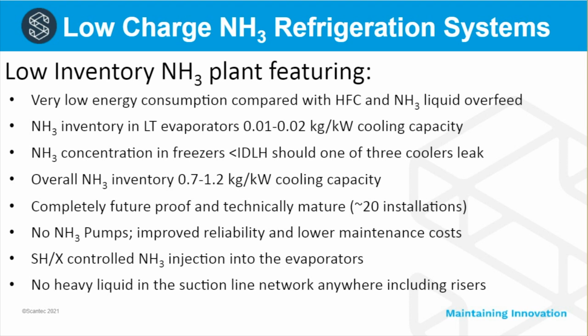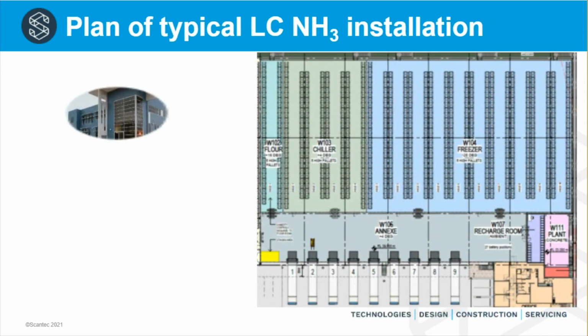And very importantly, all of the suction lines and all of the risers in the system are more or less free of heavy liquid refrigerants or liquefied refrigerants. We're running overfeed, or liquid content in the vapor line coming back to the engine room, between 1 and 5% coming out of the evaporator. So by the time it gets back to the engine room, those liquid droplets have disappeared. So the suction lines and the risers are more or less free of liquid. This is quite important. Now, first of all, let's have a look at a typical installation.